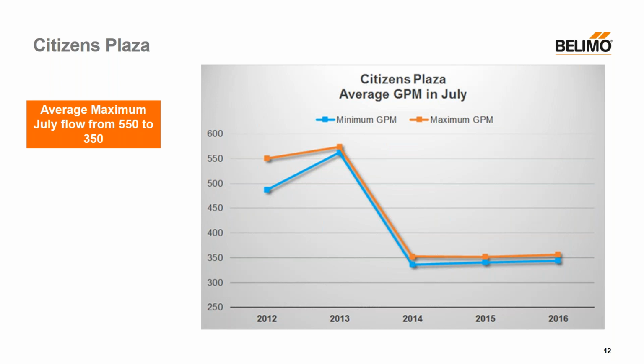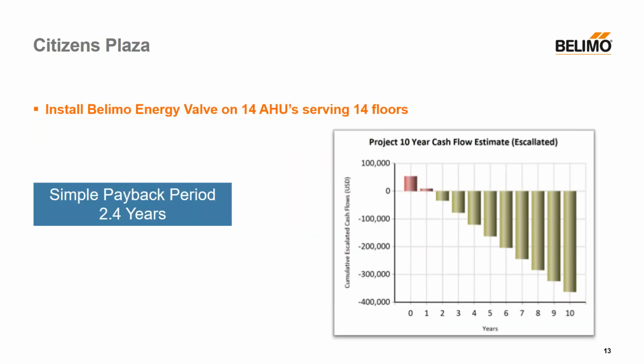During that process, somewhere between 2013 and 2015, the district chilled water plant sent a technician over to check all the equipment and to check the meter in the basement because they were certain that something was wrong with the equipment because the chilled water usage had dropped so drastically. And we were really thankful that there was no problem and that it was due to this massive drop in chilled water pumping. As you see on the chart there, we took their average maximum July flows from 550 GPM down to 350 GPM, and that's an ongoing savings today in 2020 for that building. And that whole project, the retrofit, led to a simple payback period of 2.4 years.